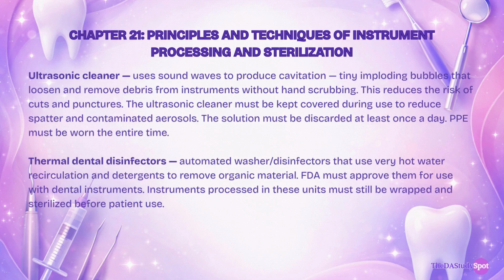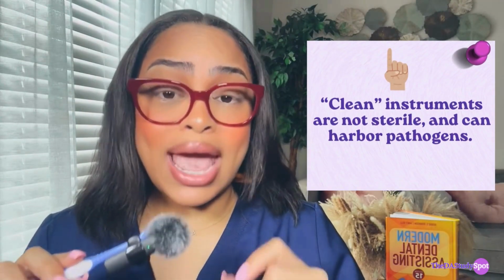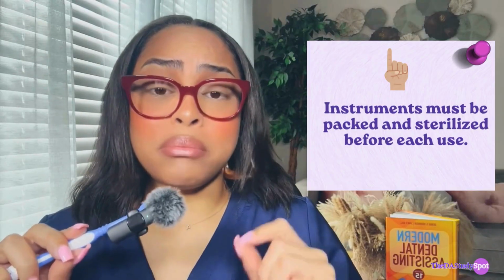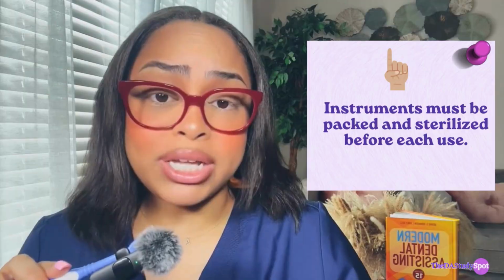Also, the ultrasonic cleaner must be kept covered during use to reduce spatter and contaminated aerosols. And at the end of each day, you must discard the solution. Again, PPE must be worn the entire time. The second method is thermal dental disinfectors. These are automated washer disinfectors that use very hot water recirculation and detergents to remove organic material. The FDA must approve them for use with dental instruments. Instruments processed in these units must still be wrapped and sterilized before patient use. Important: clean instruments are not sterile and can harbor pathogens. This is why instruments must be packed and sterilized before they are used for patient care.